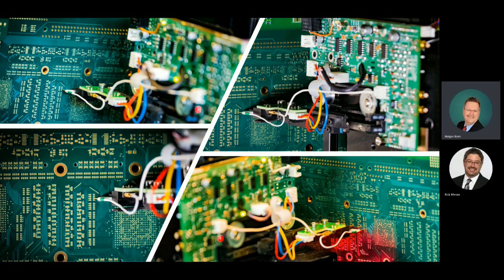That's basically how a probe tip and probe head would look. When you look at the top left picture, you see that we have approximately a 4 mil pad, where the probe tip is in front and we hit the pad. We see the probe tip itself, the electronics on the probe for the compression control, and also the probe assembly electronics where we make the measurements and have the connection to the main unit.